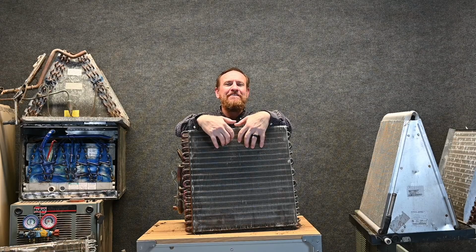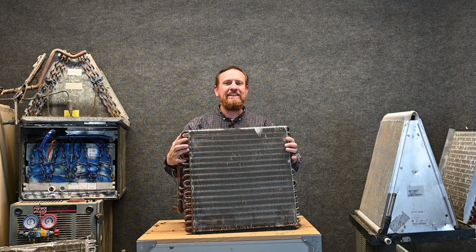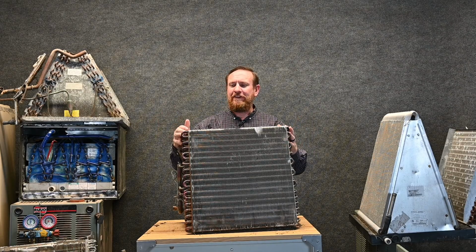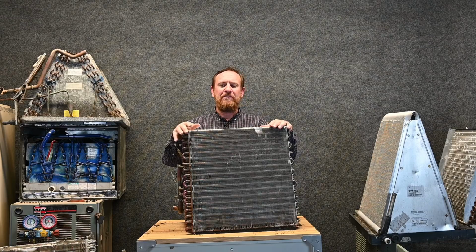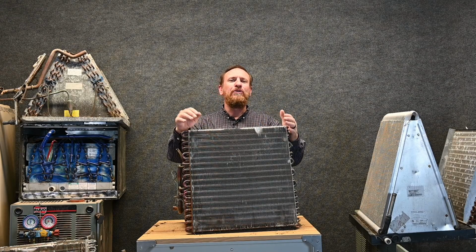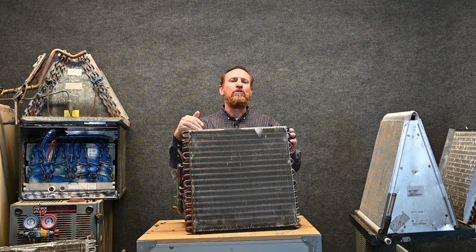Now, refrigerant leaks in an evaporator coil are going to be a huge issue. Typically, fixing the leak in the evaporator coil is simply not going to be worth it because by the time we fix one leak, another one arises and another one arises. So all manufacturers, it seems like, are having trouble with evaporator coil leaks. There are even some class action lawsuits going on right now because of evaporator coil leaking.